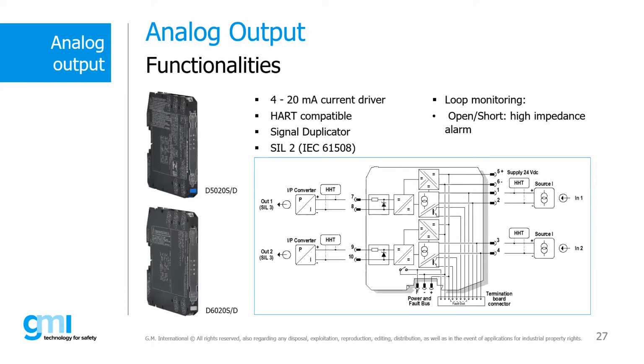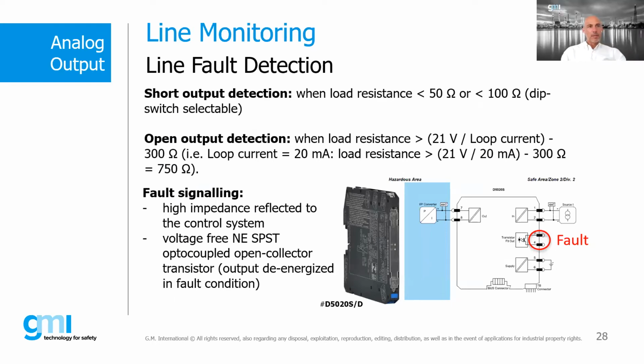And so the analog output, we have a solution with the 4-20 milliamp current drivers. Of course, we are talking about HART compatible modules with the possibility of signal duplication also. In this case, the duplication is realized by 1 input from the system and 2 outputs to the field, SIL2 valid, and also with loop monitoring, so open and short circuit reflect a high impedance alarm. And Massimo maybe can explain a little bit better about this line monitoring.